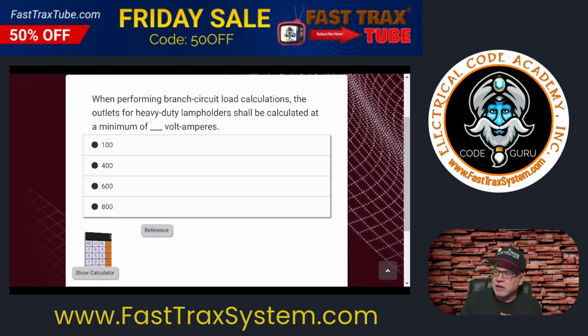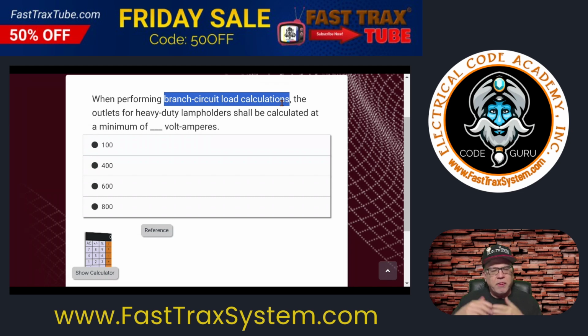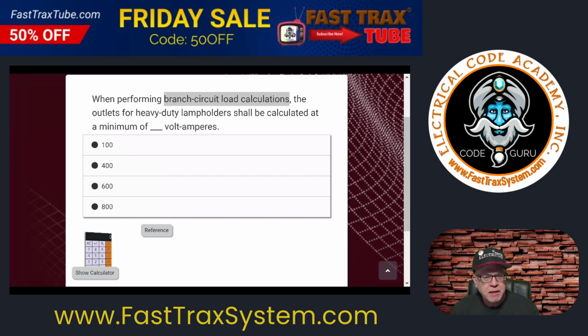And one of the things that I'm looking at right away, and it's telling me, is to perform a branch circuit load calculation. When you see something about a branch circuit load calculation, that immediately makes me think, well, I'm going to be thinking of Article 220. That's calculations. Now, we're not thinking of Part 3 because that is service and feeder calcs. We're not thinking of Part 4 in 220. That's optional. We're thinking Part 2, branch circuit applications, right? So that's where we're going to go. So let's grab our code and let's go look.